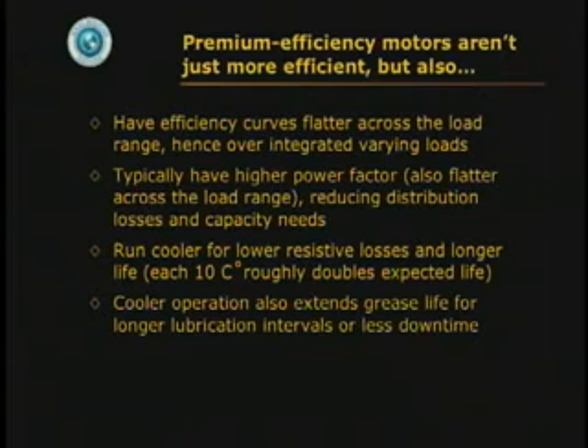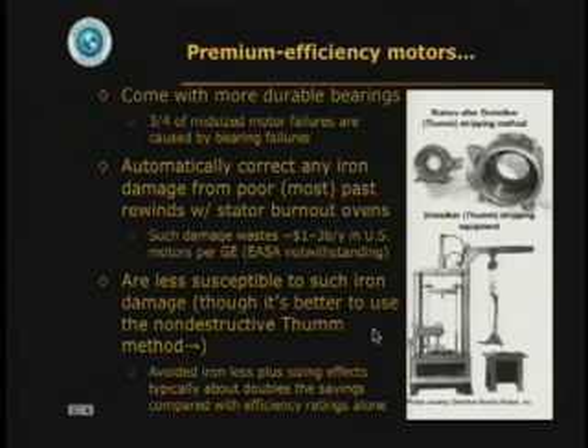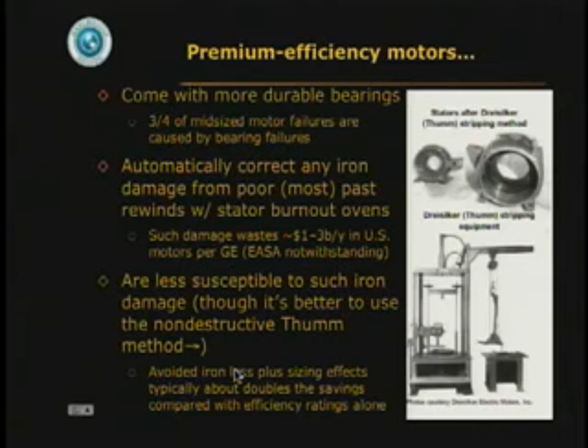They automatically correct any iron damage from poor rewinds done with the standard technique that causes about $1 to $3 billion a year worth of extra losses from iron damage. They're less susceptible to that damage, although there's a non-destructive method you can use that actually just avoids the whole problem. And it turns out that counting the avoided iron loss plus the sizing effects typically about doubles the savings that you get just by looking at efficiency ratings.